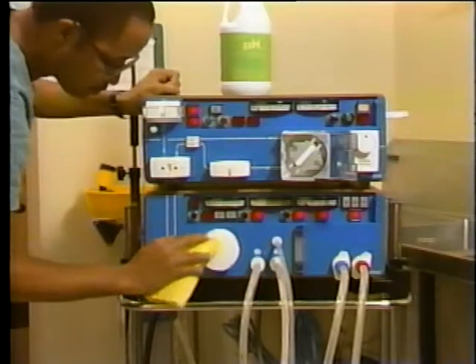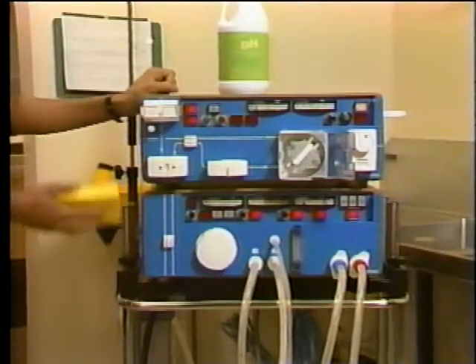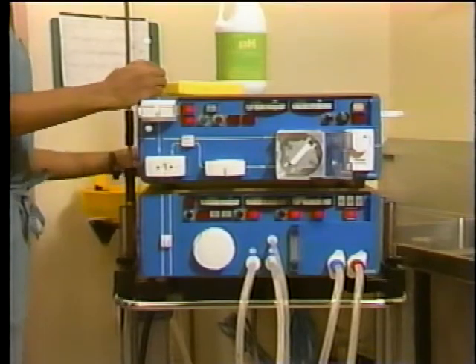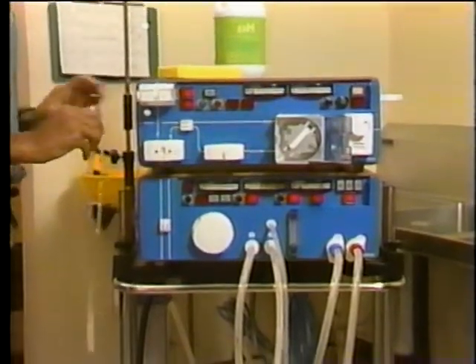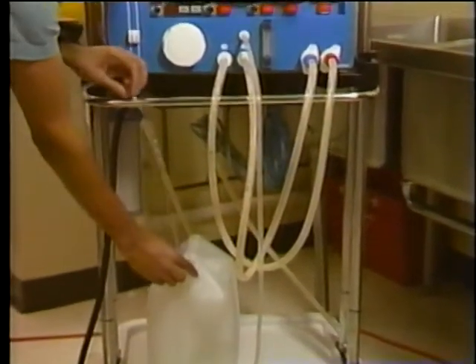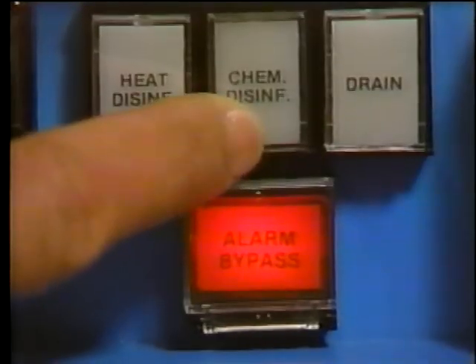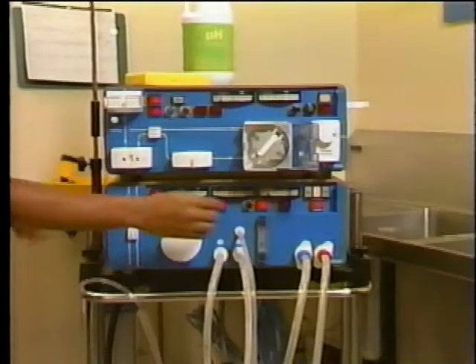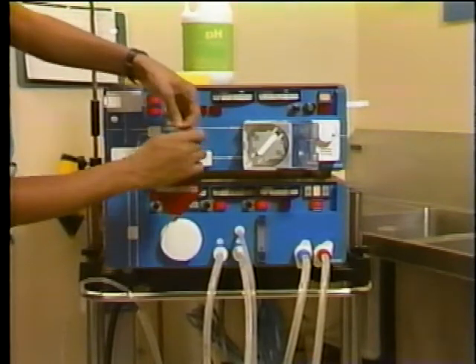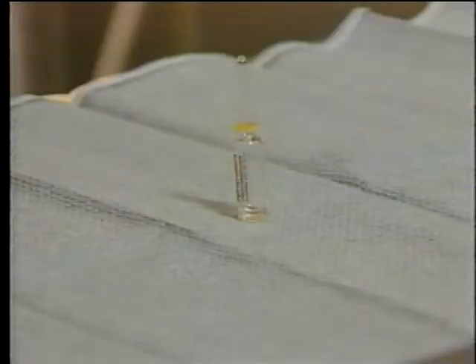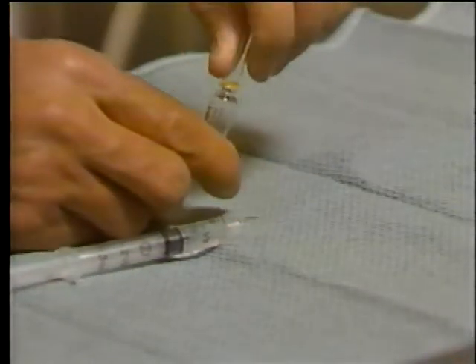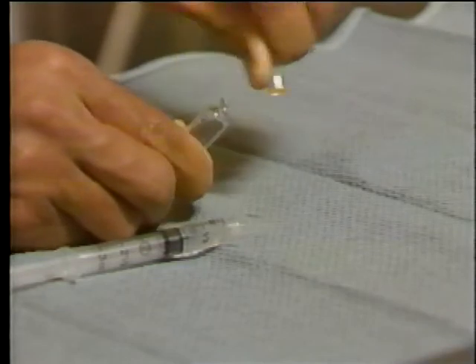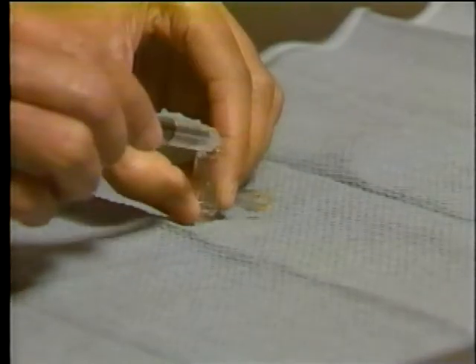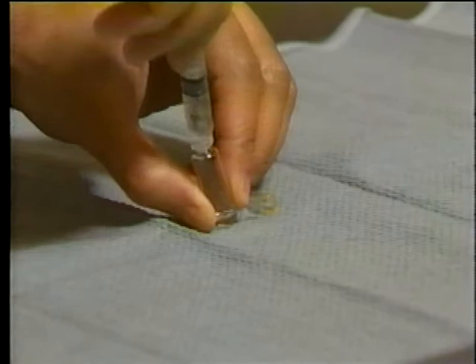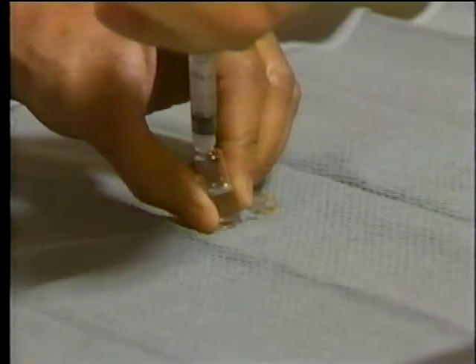For instance, most manufacturers recommend that the equipment be cleaned properly after every treatment. Sanitization or disinfection of the machine is usually performed between treatments or at least on a daily basis. Make sure that the machine is labeled or tagged if left unattended during disinfection to avoid mix-ups. Always test the dialysate lines after rinsing to detect the presence of any residual disinfecting agent. Use an appropriate residual test kit.